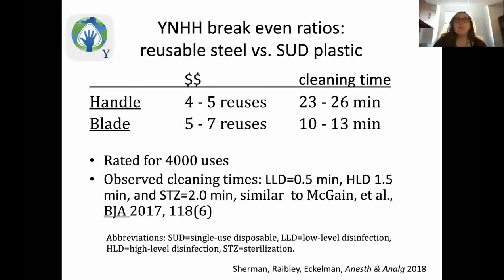So if we were to lose them, we did a break-even analysis and found that at about 4 to 5 uses of the handle and 5 to 7 of the blade, that's your break-even on costs. We also did cleaning time, which was corroborated by a study from Australia. If your cleaning time took, instead of 2 minutes overall, 23 to 26 minutes for the handle and 10 to 13 minutes for the blade—in other words, if it takes that long to clean, you have to retrain your staff. If you're losing your devices after only a few uses, you have to retrain your staff. The answer isn't to just go to disposable devices.